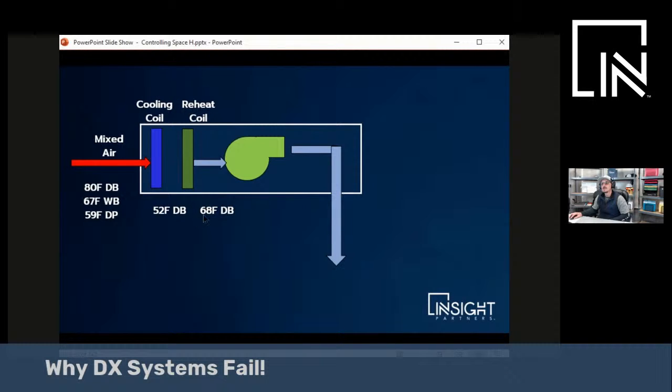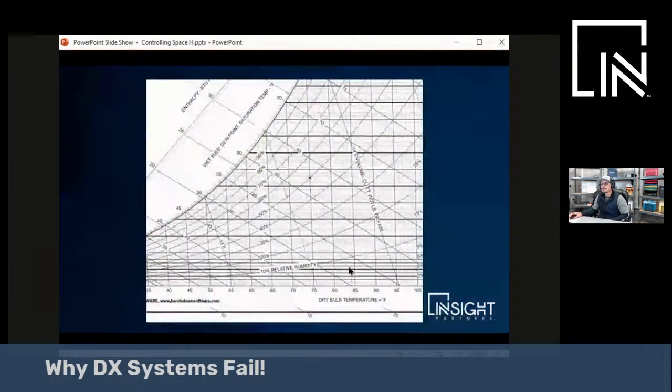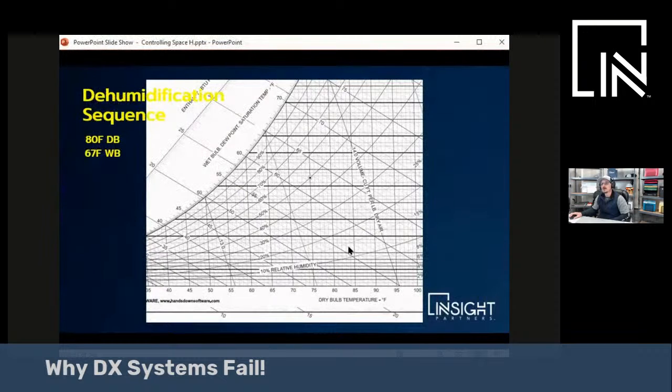We reheat it with the heating coil, let's say to 68. These are arbitrary example numbers. You pick up a few degrees with the fan. You blow this 70 degree air into the space, which is relatively warm, and everybody's good to go. Now you're dehumidifying the air and not freezing everybody out.